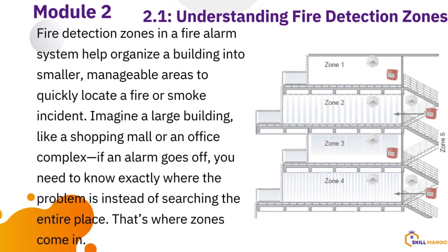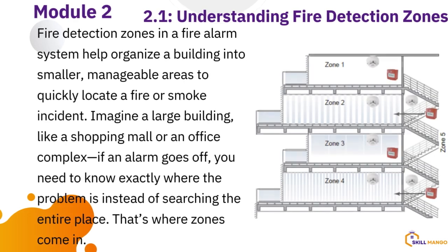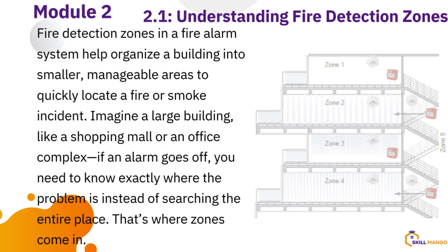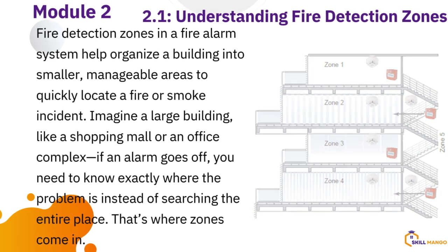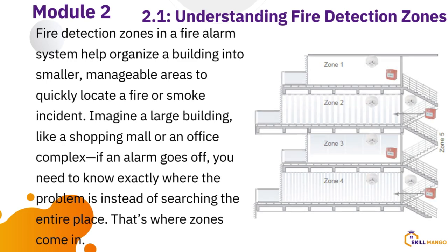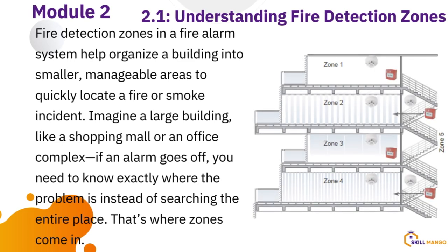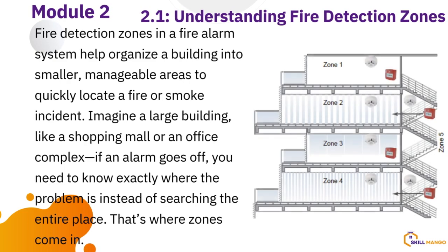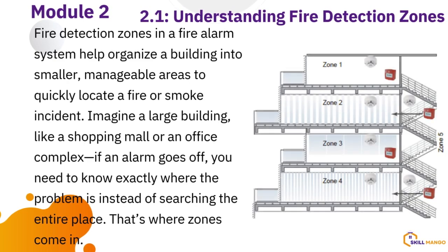All right. Then for zone 2, we run a cable again from this smoke detector to the other smoke detector by the staircase, then down to the break glass, then down to the panel zone 2. You will see the labels zone 1, zone 2, zone 3. Each of the zones has its own cable terminals for positive and negative. So you just run your cable like that, which is a loop, chain connection, then down to the panel. The same thing for zone 3 and the last zone, which is zone 4.